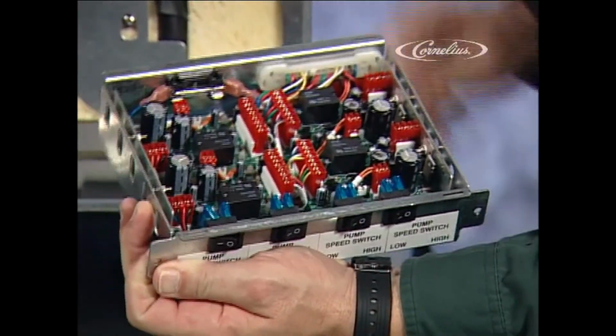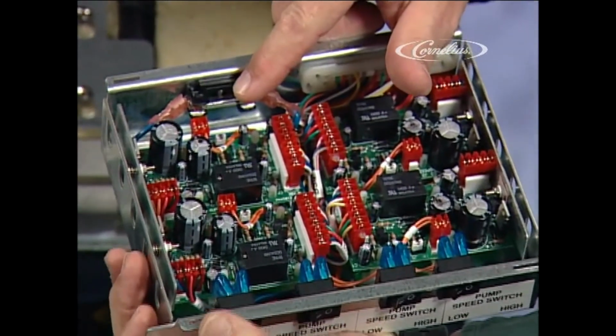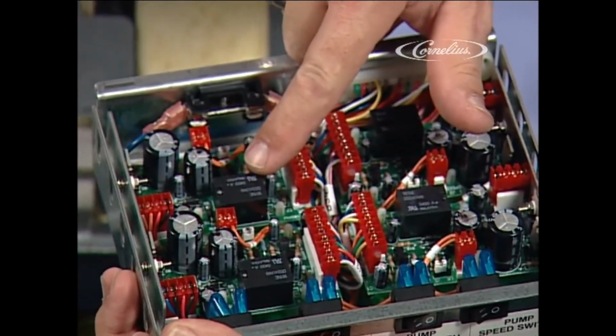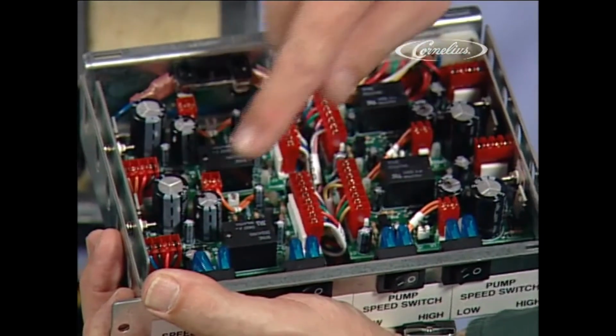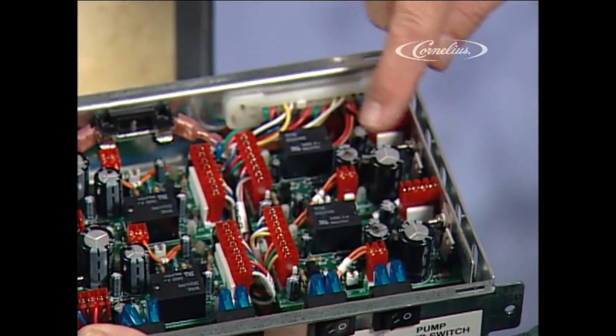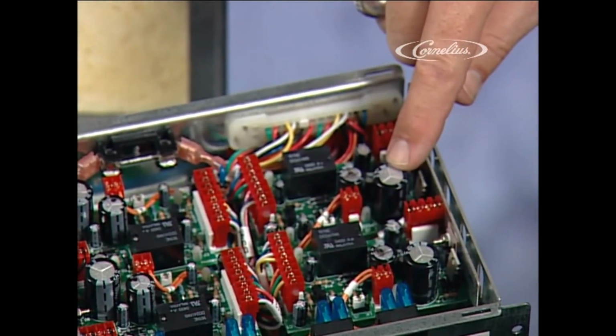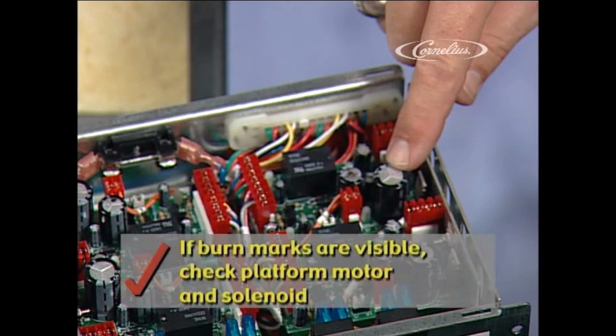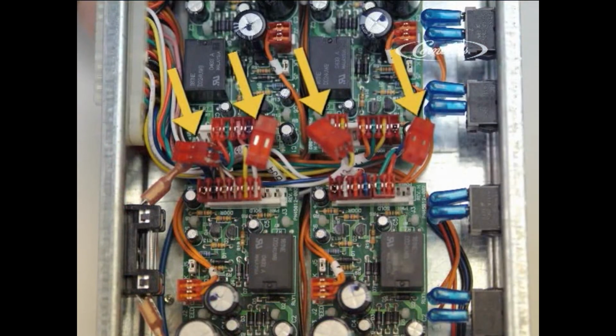Before replacing the electrical box, inspect each VRB for any burn marks on components or a deformity of the capacitors. A bad board capacitor sometimes will show up with the top of the capacitor being pushed upward. If any burn marks or blown-out components are visible, it is imperative that the dispense platform pump and solenoid for that particular head be checked. This condition indicates a possible shorted solenoid coil or motor, and they should be checked and replaced if necessary before activating the replaced VRB. Pull all the 26 volts AC inputs off of each board, leaving just one remaining.